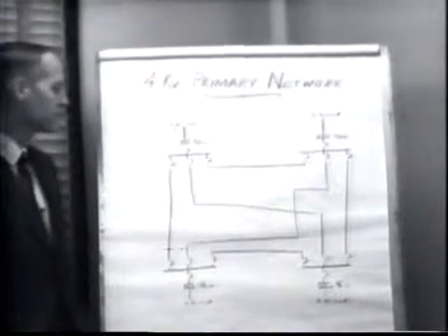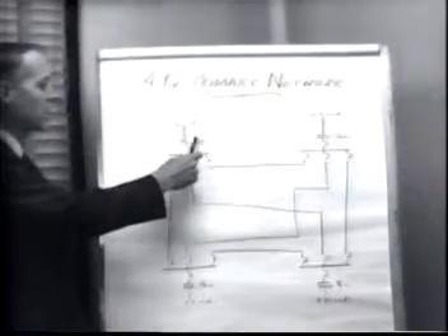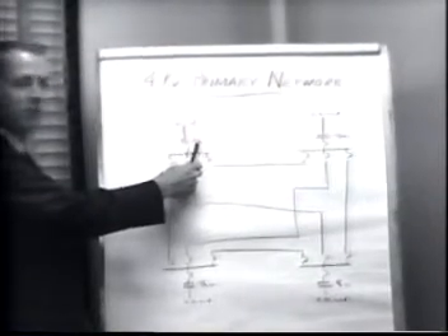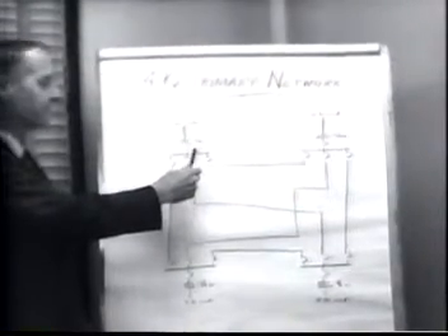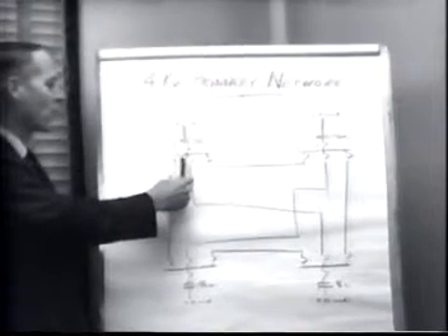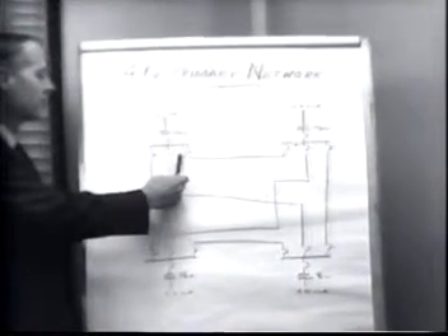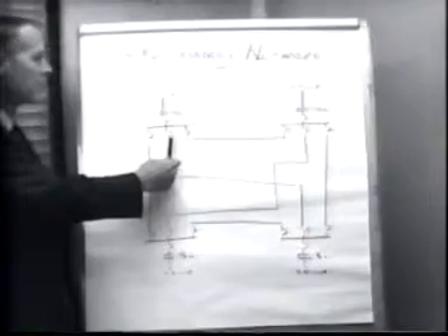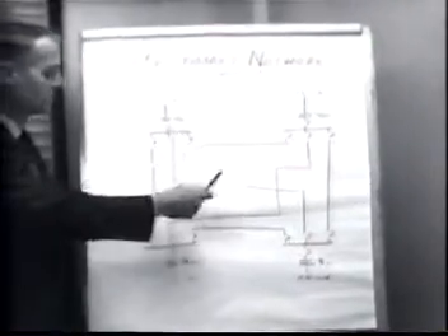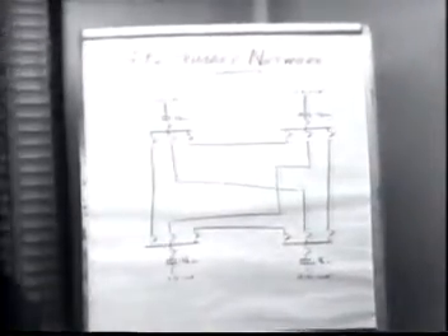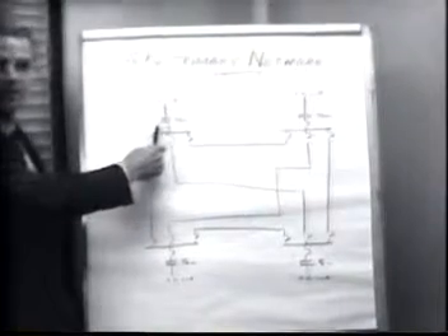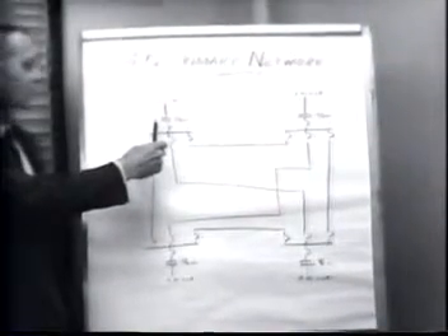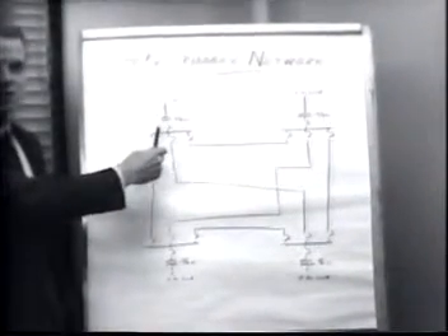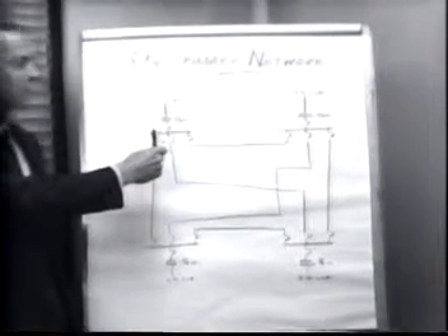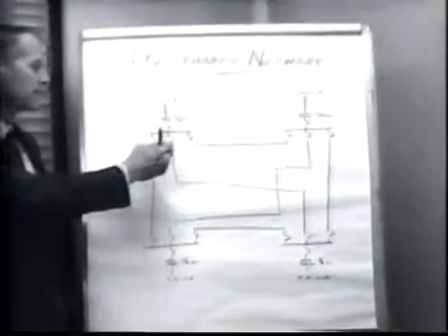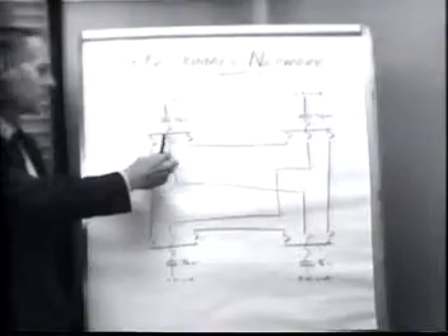Each substation consisted of a transformer from 13,000 volt to 4160 volt, three-phase, four-wire, and a series of tie line feeders extending from each substation to every other substation. The 13 kV lines feeding the transformers were from separate substations as much as possible, from separate bus sections in a given substation.